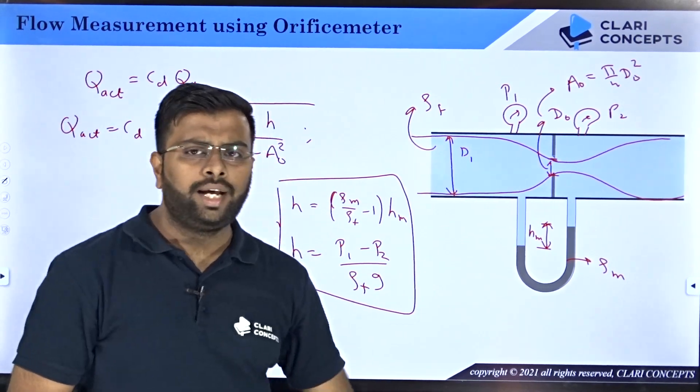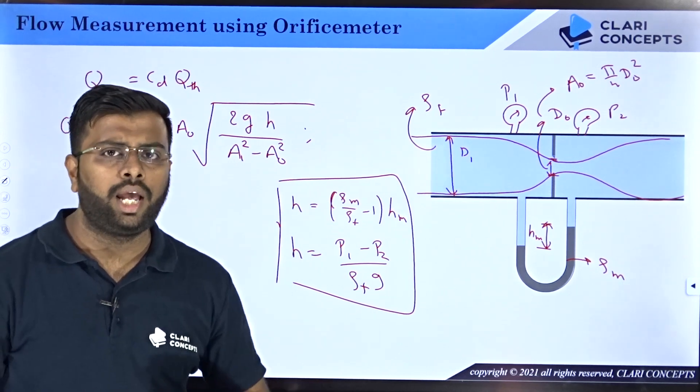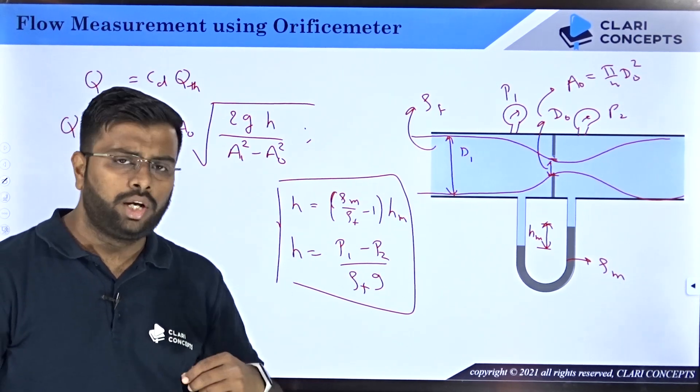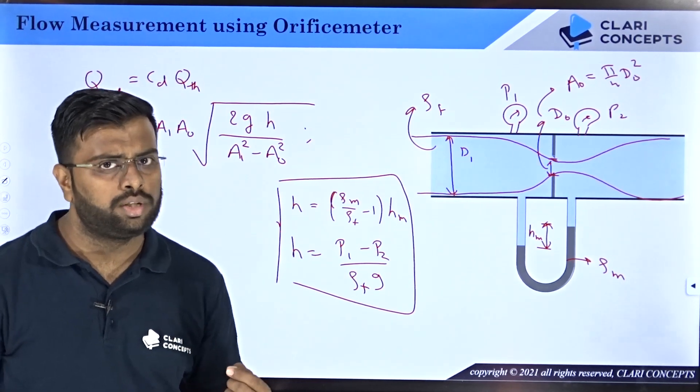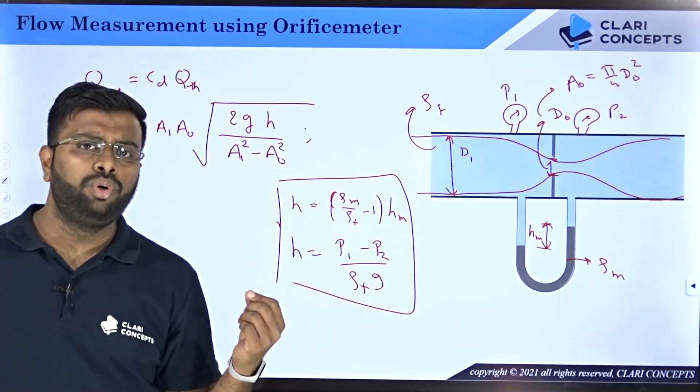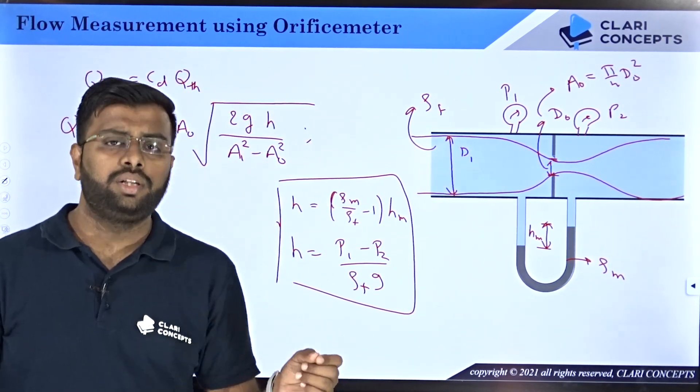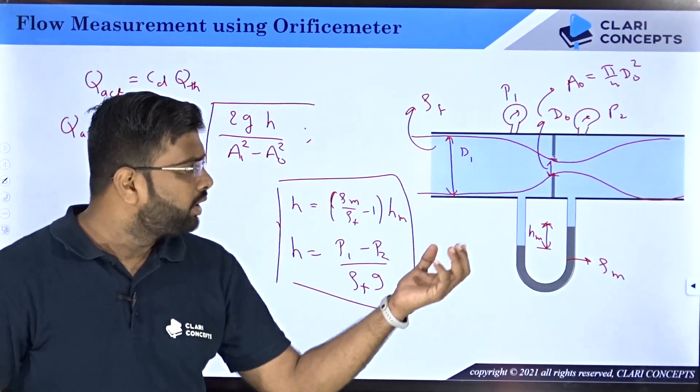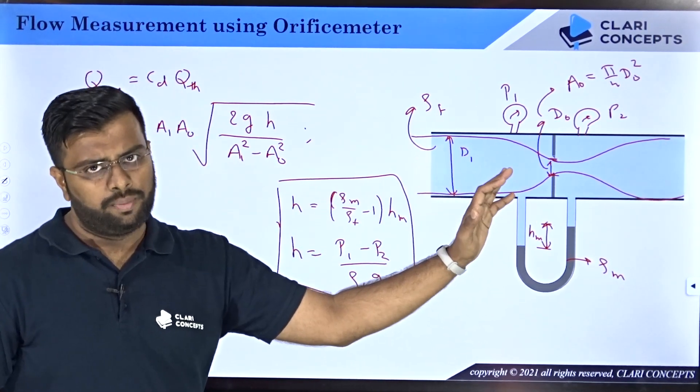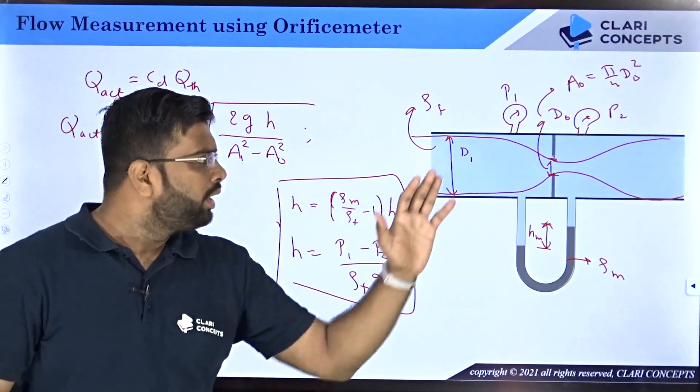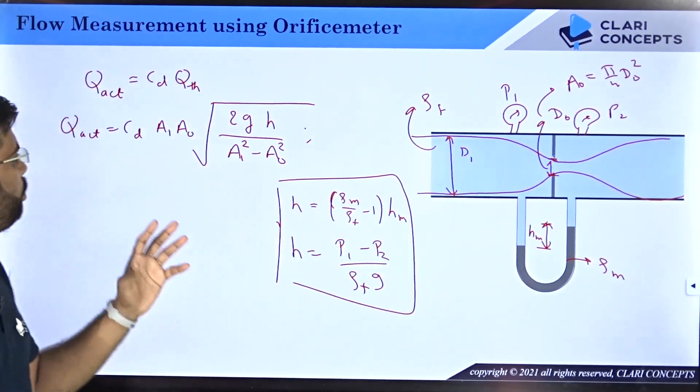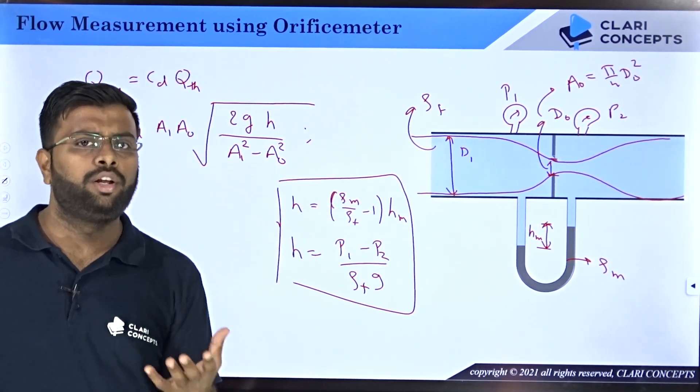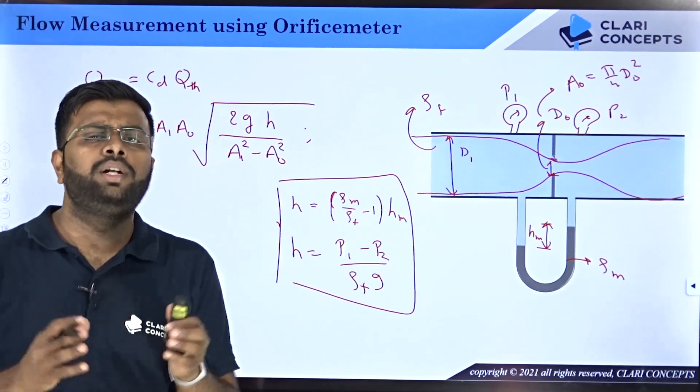Here only one difference will be there. C_d, as I said, this orifice meter is not that great in accuracy. You are going for a cheaper device, you will always lose the accuracy. In case of venturimeter, the theoretical flow was almost 98% accurate to that of the actual value of flow rate. But here the accuracy will be almost 60-65%. The value of C_d will be provided to you by the manufacturer of the orifice meter or the designer of the orifice meter.